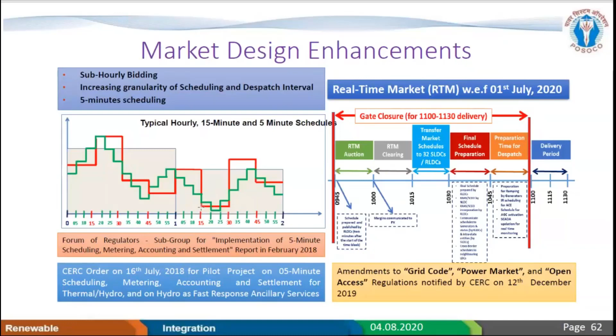In terms of market design, there is a pilot project. Presently we are at 15-minute time blocks. There is a plan to go to 5 minutes in the near future. Presently, a pilot project is envisaged to gain experience before we actually move on. That means my scheduling will be of 5 minutes, so my ramp and flexibility requirement would come down. The other aspect is that we have now got the real-time market. Earlier the SLDC did not have a market close to real time. We had other venues, but now he can directly bid and get, within a maximum of 1.5 hours. So this is the real-time market we have as of now.